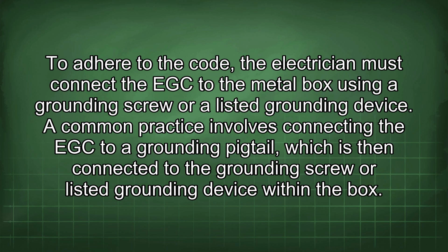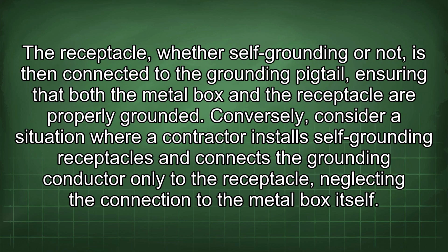To adhere to the code, the electrician must connect the EGC to the metal box using a grounding screw or a listed grounding device. A common practice involves connecting the EGC to a grounding pigtail, which is then connected to the grounding screw or listed grounding device within the box. The receptacle, whether self-grounding or not, is then connected to the grounding pigtail, ensuring that both the metal box and the receptacle are properly grounded.